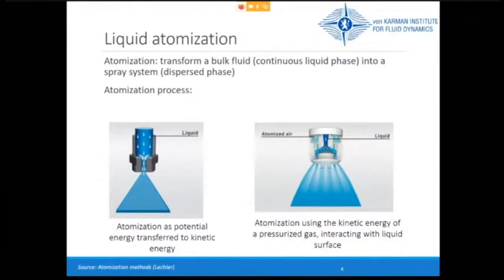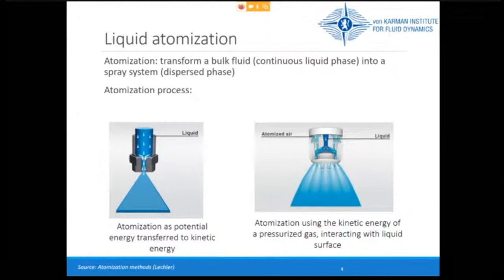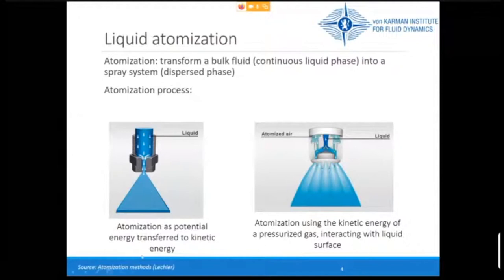Water curtains are based on sprays, and sprays are based on atomization — a phenomenon which transforms a bulk fluid, considered as the continuous liquid phase, into a spray system of dispersed phase. The atomization process can be divided into two categories: the first uses only the liquid, where potential energy is transferred to kinetic energy; the second uses pressurized gas interacting with the liquid surface. For water curtains, only liquid atomization is used.